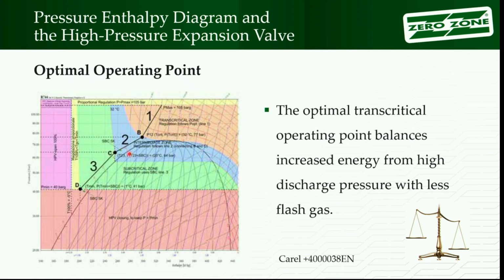You have a transition point. I think a lot of times they'll say the transition point, decide where it wants to stop trying to be subcritical and where it wants to be transcritical, and they just set a target for its control. When you get up above the transcritical point, now it's looking at an optimal pressure based on the leaving temperature of the gas cooler. And there's a formula that's been derived, theoretically tells you what is that optimum pressure based on your leaving temperature. And it's pretty much the same formula for everybody, right? Some of the guys may have tweaked it a little bit, but the compressor guys are pretty much using the same formula. All the control people are using the same formula.